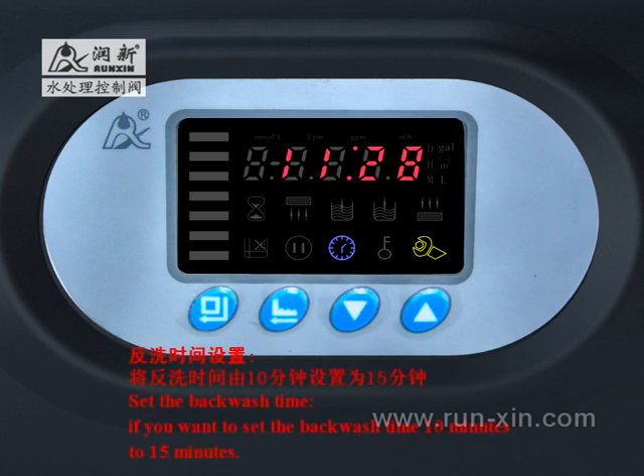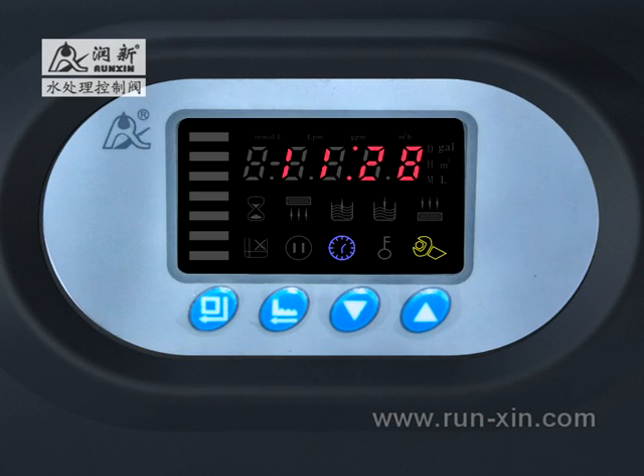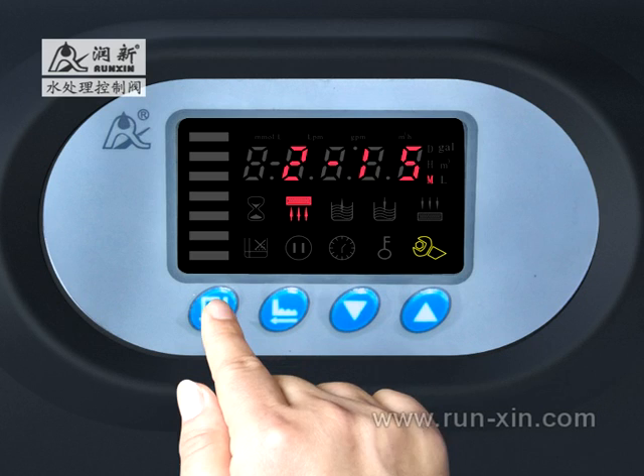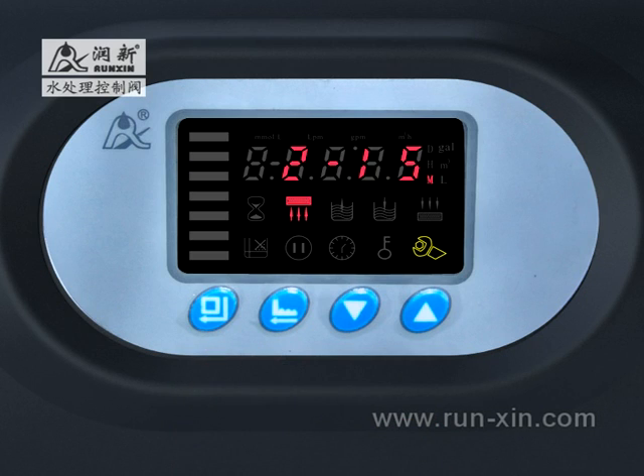Backwash time setting. Change the backwash time from 10 minutes to 15 minutes. Press the up or down button until the backwash symbol lights up. Press the menu button to get into inquiry state. The value 10 and the setting symbol start flashing. Press the up button continuously until 10 changes to 15. Press the menu button. You will hear a sound of D. The symbol stops flashing. The program returns to inquiry state.